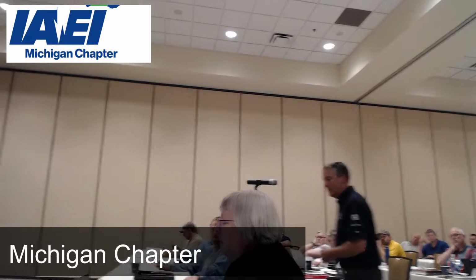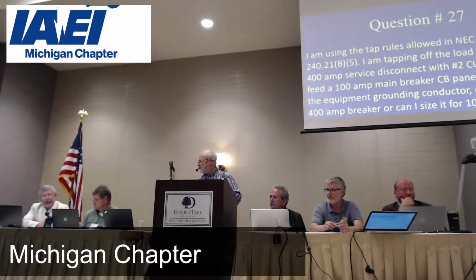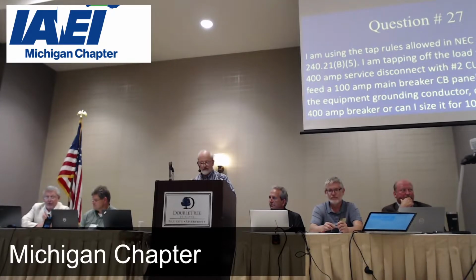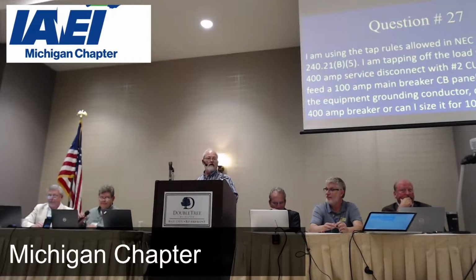Yeah, the 100 amp won't see it, and that's also why the tap rules have a 10-foot tap rule where you can go down to 10% of the size of the conductor you're tapping from, or the overcurrent device ahead of it, and the 25-foot tap rule where you can only go to 1/3 the rating of the overcurrent device ahead of it, because you're introducing a tremendous amount of impedance from that larger conductor that you're tapping off of. So you want to make sure that you don't increase your impedance to the point where that larger overcurrent device won't trip. Okay. Anything else on that one?